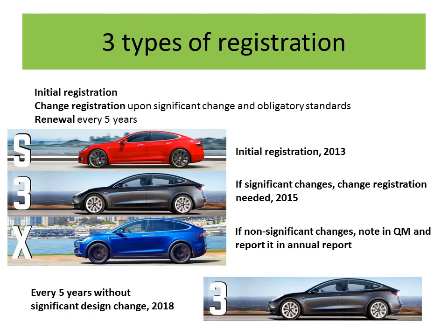Let's illustrate the important registrations of medical devices with the example of Tesla. If you wish to bring Model S to the Chinese market, you start an initial registration. Upon significant change, you have a change registration for Model 3. Imagine Model X has only a different color and belongs to a variant of the initial model. You can market Model X without any regulatory action with the Chinese authority.